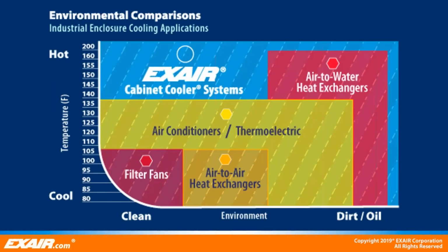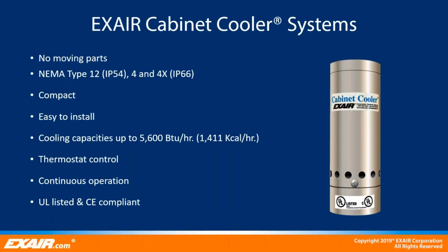Here's a visual chart to explain the temperature and environmental conditions each of the cooling systems performed best in. EXAIR cabinet coolers exceed the BTU per hour characteristics of most. They exceed the maximum operating temperature of most and can withstand the harshest conditions while still producing a very low total operating cost. EXAIR's compressed air operated cabinet cooling systems are a low cost, reliable way to cool and purge electronic control panels. There are no moving parts to wear out, and no filters to replace, eliminating the need for constant monitoring.